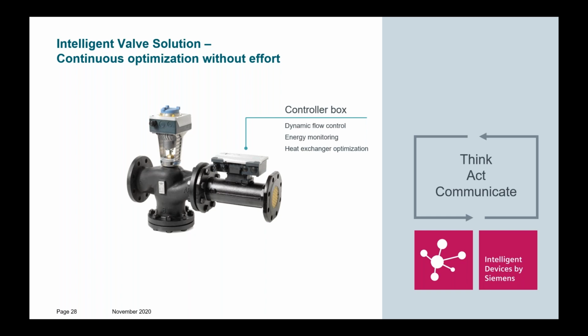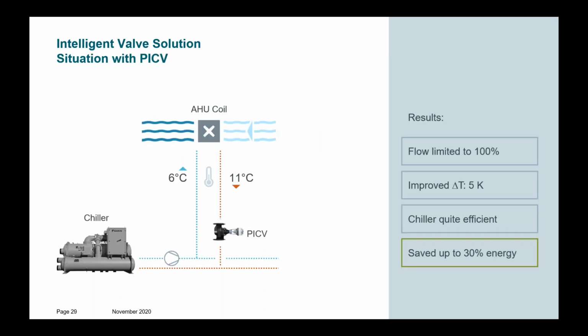So it's just more energy efficient to pump around 500 cubic meters with 6 Kelvin DeltaT instead of pumping around 1000 cubic meters with 3 degrees DeltaT. So the net power consumption of the generation and also of the network will drop clearly with increased DeltaT. Now, how does this work actually? Here we have the example from Luca with the PICVs. This is a very good first step. We keep the maximum flow under control to the design flow, and with that, we have already increased DeltaT to a certain level and saved some energy there.